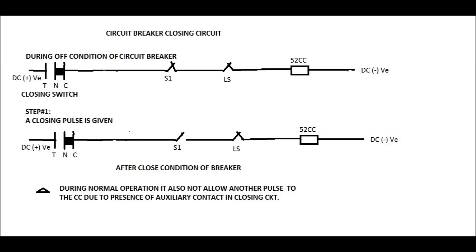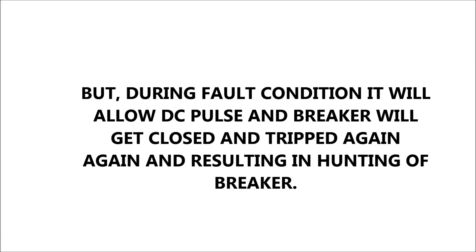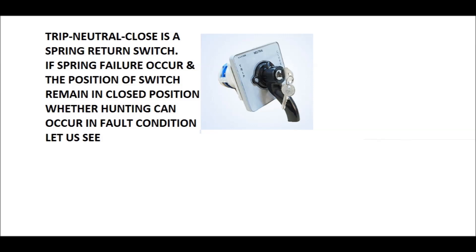In the presence of the auxiliary contact, it will not allow another DC pulse to the closing coil. But in fault conditions, as soon as the breaker trips, it will allow the DC pulse to the closing coil again, which will operate the breaker to make it ON. Since the fault is still present, it will trip again — a situation arises where it will close-trip-close-trip, that is, hunting of the breaker, thereby causing failure of the breaker.